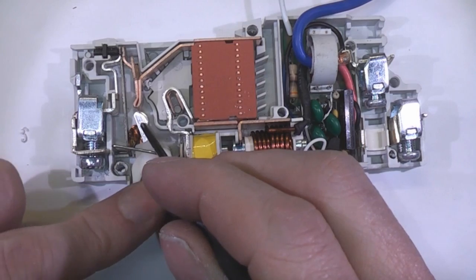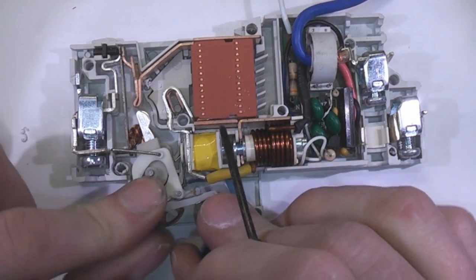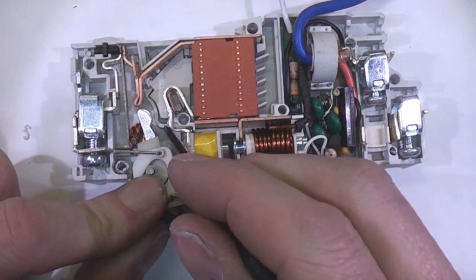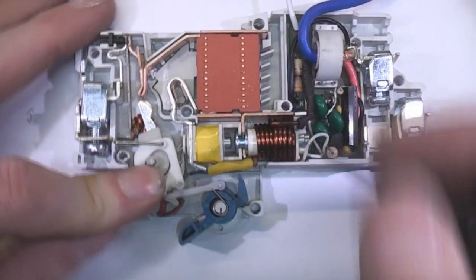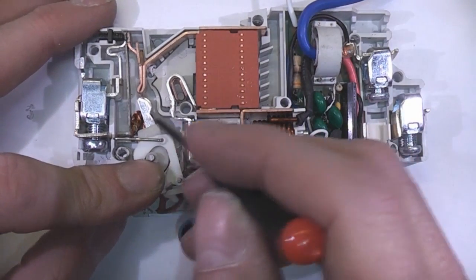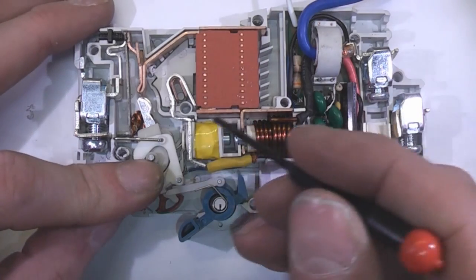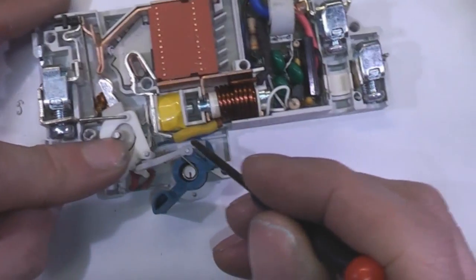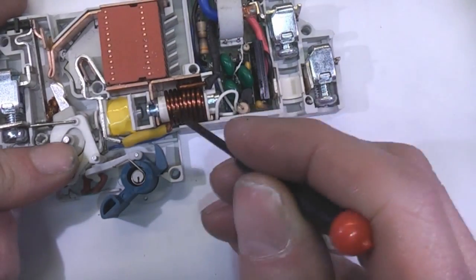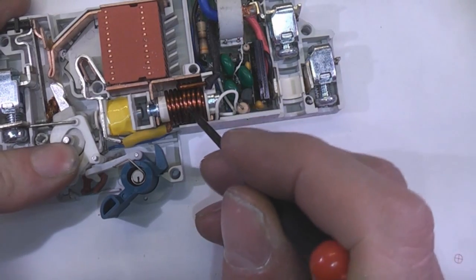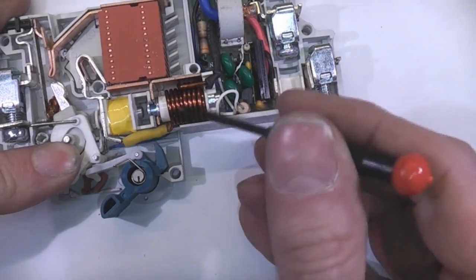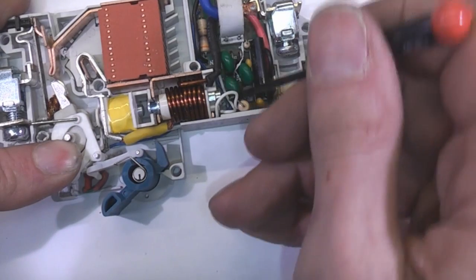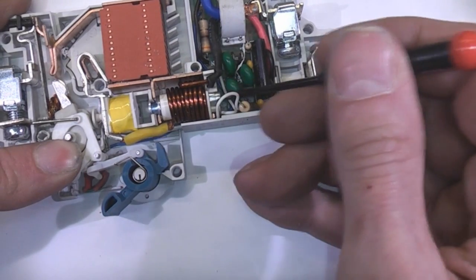So this is one of the actual contacts, and this is the other contact. I'll talk about this stuff in a minute, but the actual current goes through here, across here, up, and then through this coil. So obviously this is a big chunky coil, so this is the overcurrent protection. When the current through this coil gets too high, the magnetic field causes this lump of metal to go in and trips it out quickly.